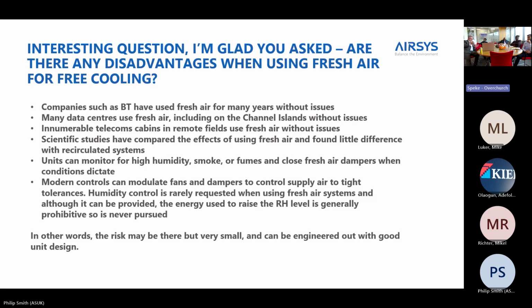So in reality, if you're going down the fresh air route, then humidity control tends to be relaxed, shall we say. You won't get 50 plus or minus 5 whilst you're controlling with fresh air, for example. But most IT companies and data centers really aren't that worried about the RH, as long as it's not so low as to cause static. So in other words, no, we don't believe that there is a risk, and where there is, it's engineered out by good design.